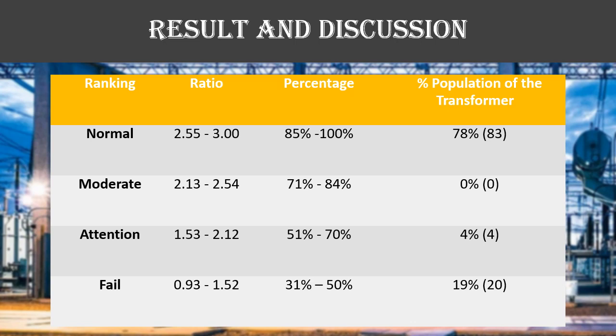Based on the exploration, we have defined the rankings for the transformer. For the normal condition, the ratio is 2.55 to 3.00, which is a percentage within the range of 85% to 100%. Moderate is 2.13 to 2.54, which is about 71% to 84%. For attention, it's about 1.53 to 2.12, which is 51% to 70%. And for a failed transformer, the ratio is 0.93 to 1.52, which is 31% to 50%.